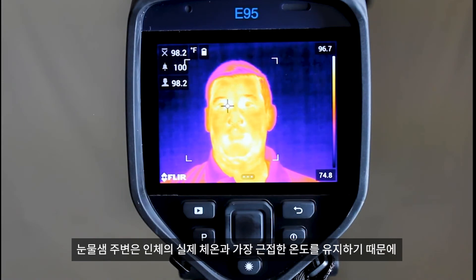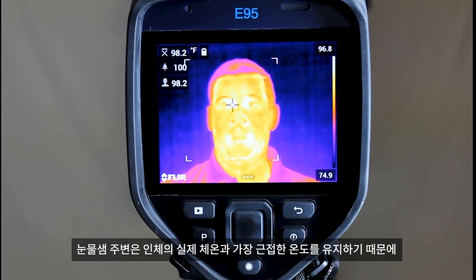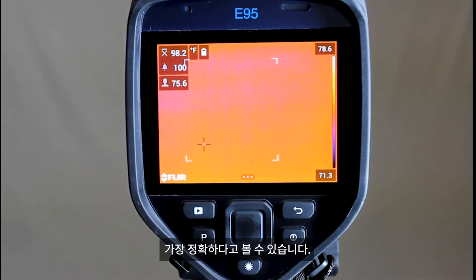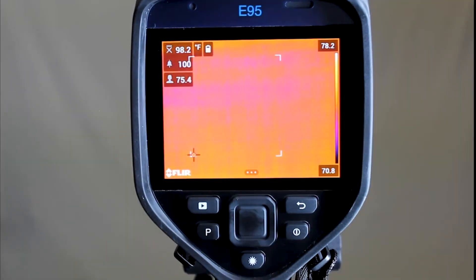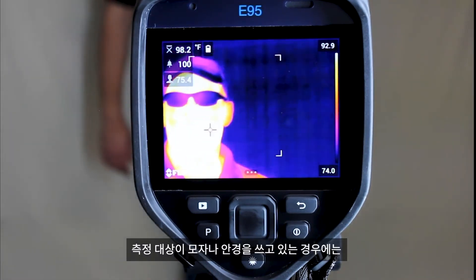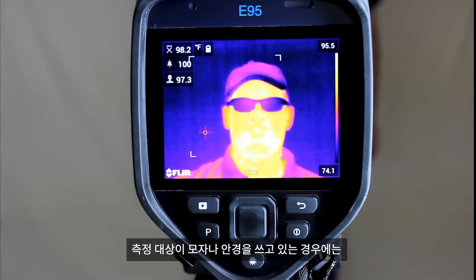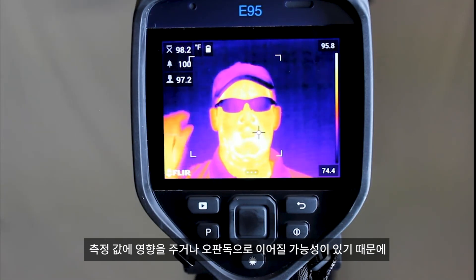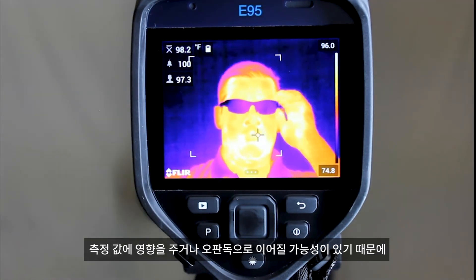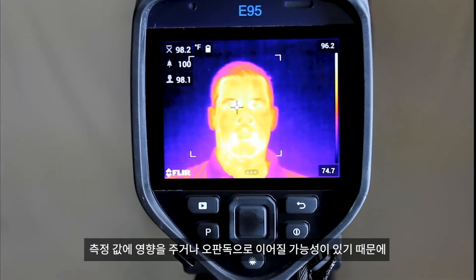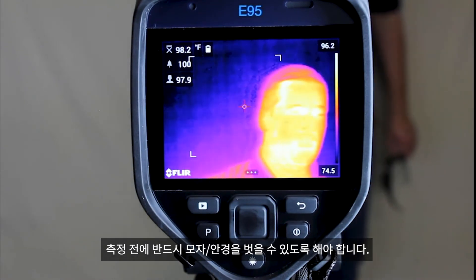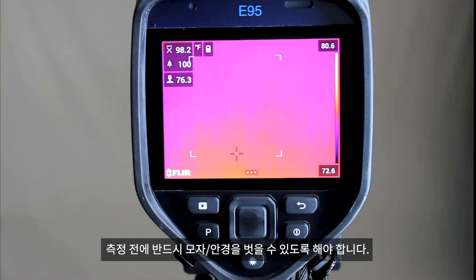This location provides the closest temperature correlation to human core temperature. During the screening process, you will want to make sure that all hats and glasses are removed prior to screening, as these can impact our readings and provide false information.